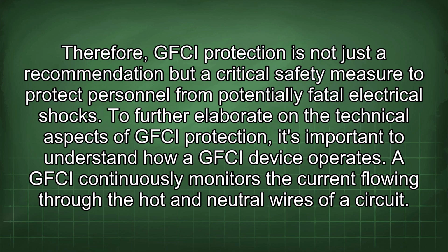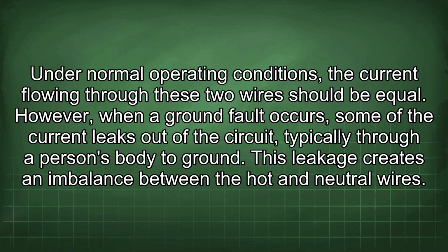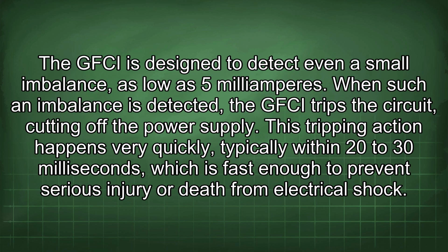A GFCI continuously monitors the current flowing through the hot and neutral wires of a circuit. Under normal operating conditions, the current flowing through these two wires should be equal. However, when a ground fault occurs, some of the current leaks out of the circuit, typically through a person's body to ground. This leakage creates an imbalance between the hot and neutral wires. The GFCI is designed to detect even a small imbalance, as low as 5 milliamperes.